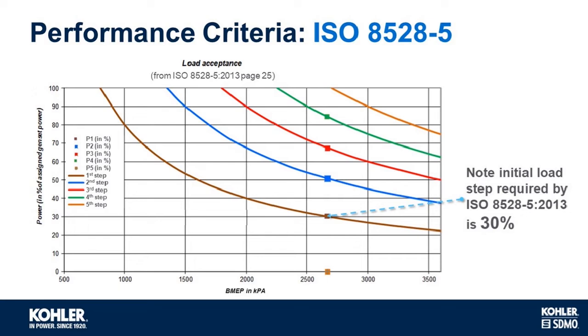As well as setting out governor classification, it also details the load steps that should be used. So looking at the graph, as you can see, we've got 5 curves, the brown being the initial load step and the others being the subsequent steps. The BMEP, or pressure, within the engine cylinders determines the percentage and number of load steps for the generator to reach 100% load. The example here uses a typical BMEP of 2,700 kPa from a modern fast response diesel engine.